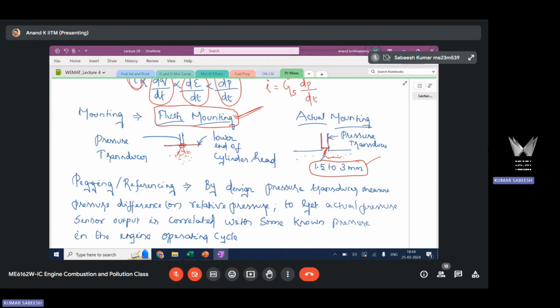Also, since the sensing element is not directly exposed to gases, there may be some time lag. But the time lag is generally minimal because pressure is a wave phenomenon. Pressure will equilibrate quickly. Wherever there is a pressure difference, it will try to equilibrate as quickly as possible. That is one advantage here. It won't affect much, but nevertheless, there will be some time lag as compared to flush mounting.